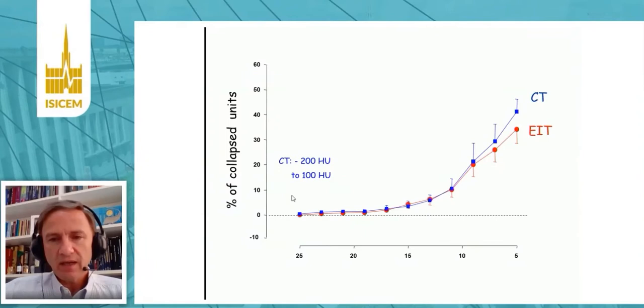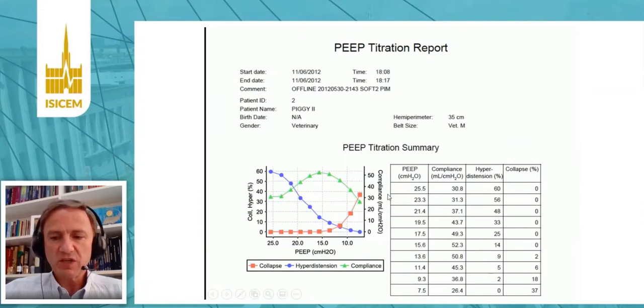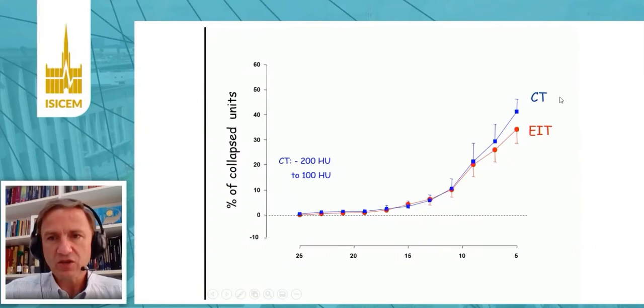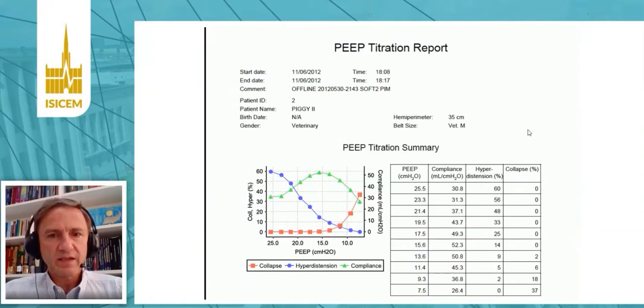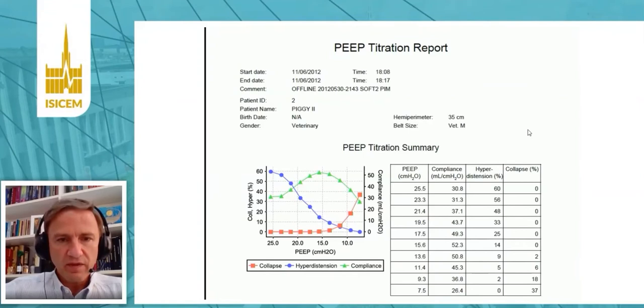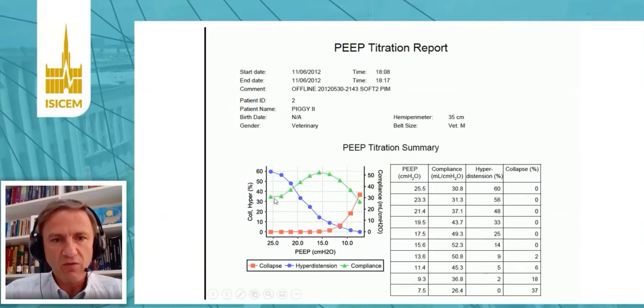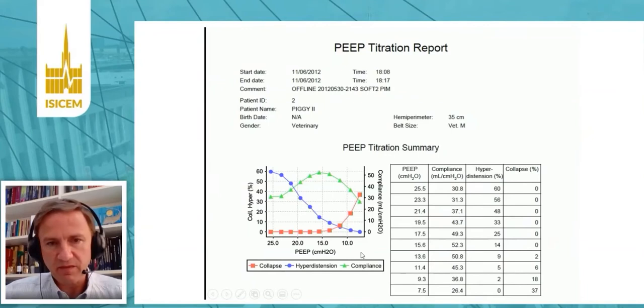Later on, we did some comparison of collapse estimates by CT and by EIT in experiments in pigs, and we showed a very nice correlation between CT estimates and EIT. Nowadays, some devices can provide automatic PEEP titration with an online display where you see lung collapse in red, hyperdistention in blue, and compliance of the respiratory system in green. Then you can pick a certain PEEP level that gives you the best compromise between collapse and hyperdistention.